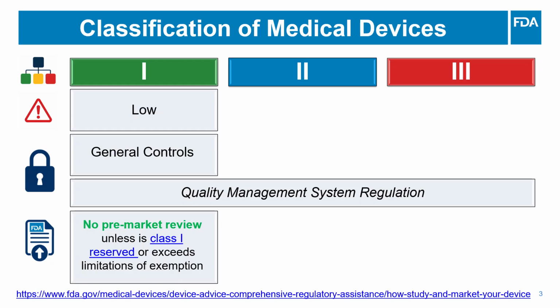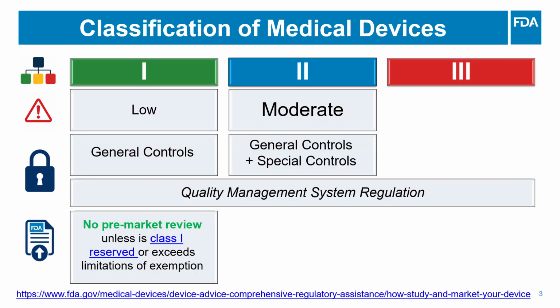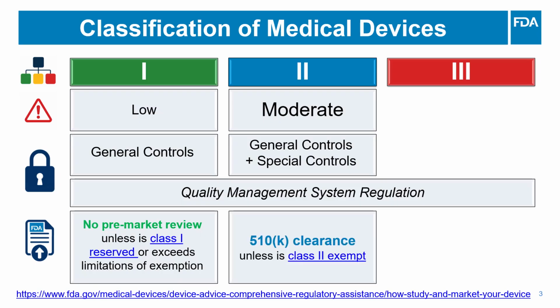FDA classifies into Class 2 devices with moderate risk, for which general controls alone are insufficient to provide reasonable assurance of safety and effectiveness, but there is sufficient information to establish special controls to provide such assurance. Special controls are usually device-specific and may include performance standards, post-market surveillance, specific labeling requirements, or pre-market data requirements. Most Class 2 devices require a pre-market notification that is known as 510(k), where companies demonstrate that their devices are as safe and as effective, that is, substantially equivalent to a predicate.